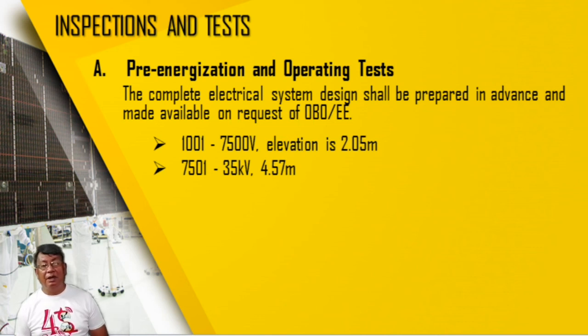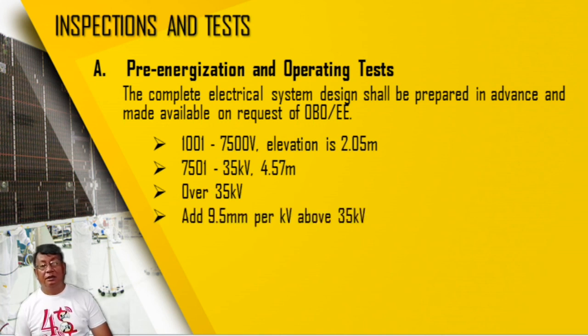If it is 7501 to 35 kV voltage, then the overhead distance shall be 4.57 meters. Or if it is over 35 kV, we add 9.5 millimeter per kV above 35 kV. So for example, if our transmission line or conductor carries 69 kV, it must have a 9.5 millimeter increase of the distance per kV above 35. So that's how to compute for the elevation of the overhead conductor.